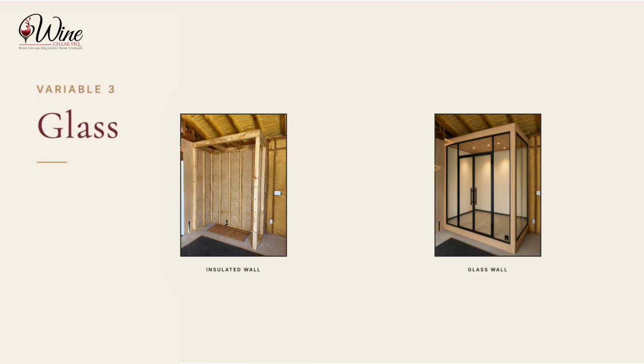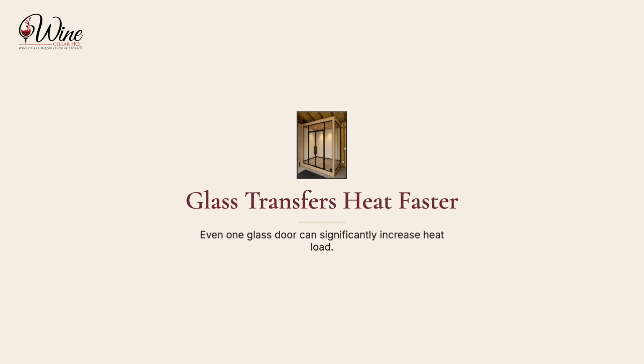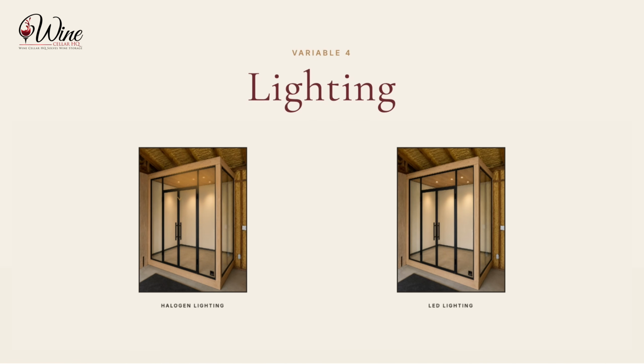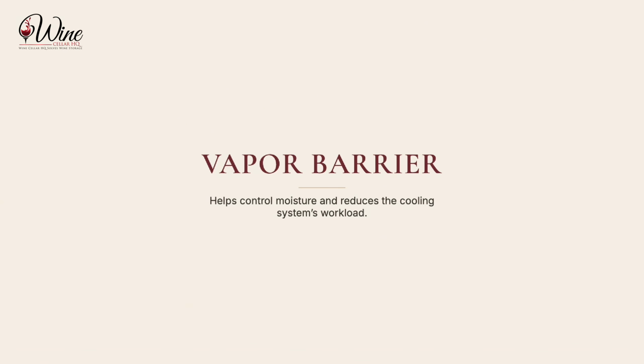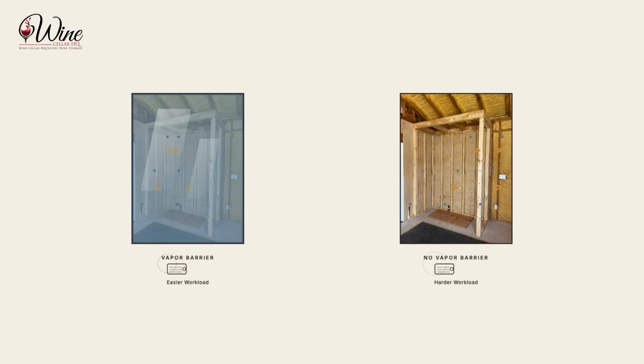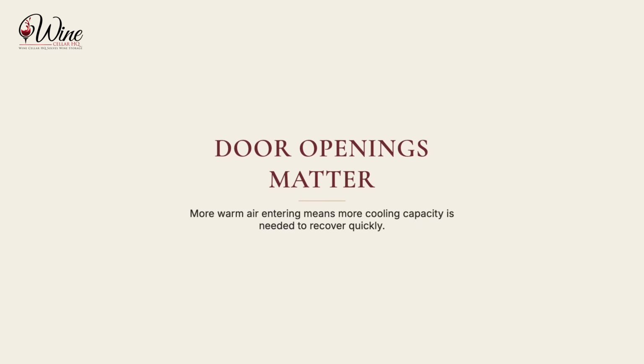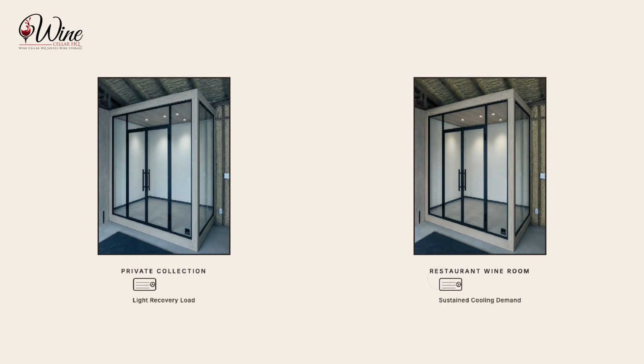Glass. Any window, glass door, or glass wall, glass loses and gains heat far faster than an insulated wall. A single glass door can add roughly as much heat load as an entire solid wall. Lighting. Incandescent and halogen bulbs actually generate meaningful heat inside a sealed room. LEDs run much cooler. Vapor barrier. This affects both moisture control and your effective heat load. Skipping it makes your unit's job harder. How often the door opens. A private collection opened occasionally is a light load. A restaurant wine room opened dozens of times a night needs real recovery capacity built in.